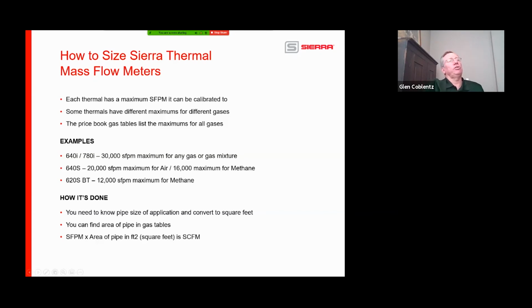So each thermal meter has a maximum standard feet per minute it can be calibrated to. I showed you all those in the gas table list. Some of them have different maximums for different gases, and the price book has the maximums for all of the gases. So for example, 30,000 standard feet per minute maximum for any gas or gas mixture. 640S, 20,000 standard feet per minute for air. 16,000 maximum for methane. 620S BT, 12,000 standard feet per minute maximum for methane.